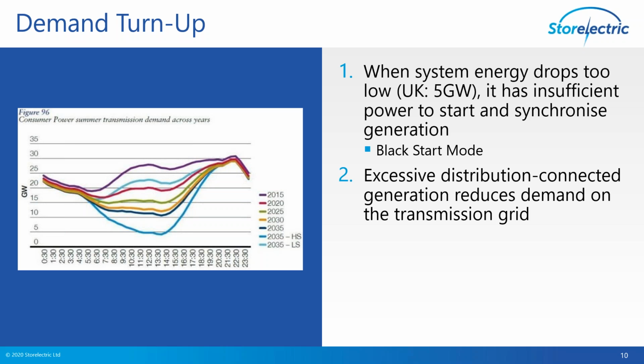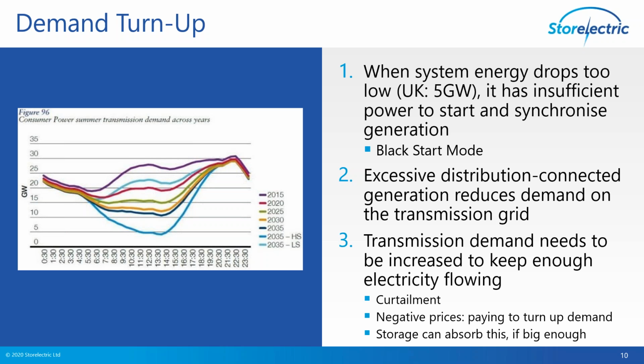Unfortunately, they underestimated the amount of solar on the grid at the time, and they also didn't consider what happens if the wind's blowing at the same time. So the first time they came across the worst case 2035 scenario was actually the same year, in August 2015, for which reason they've never put out this curve since. So there is a big issue that we need to keep a certain amount of electricity flowing through transmission grids, even when it's not needed, because it's being sucked into distribution grids that have enough of their own generation.